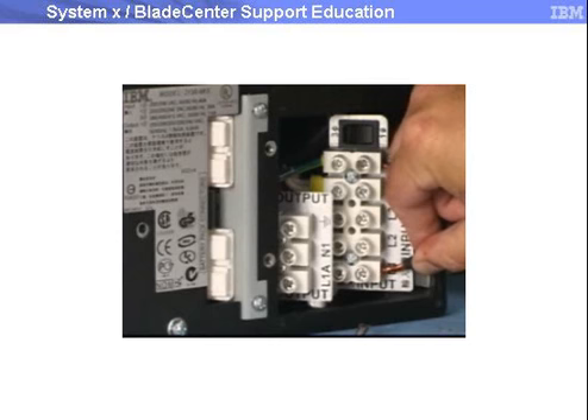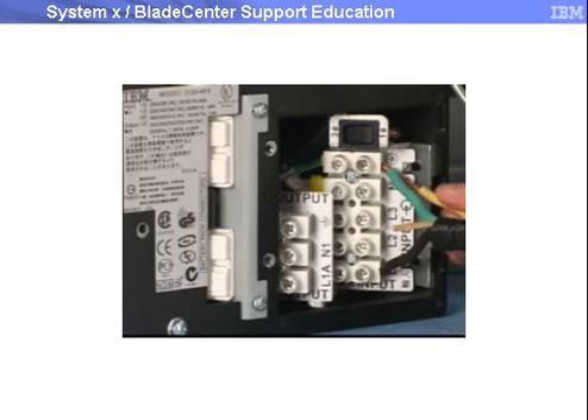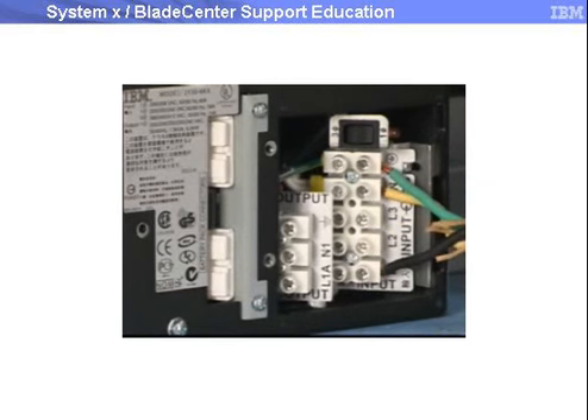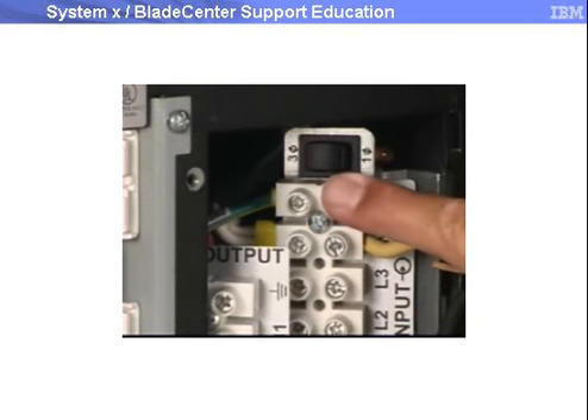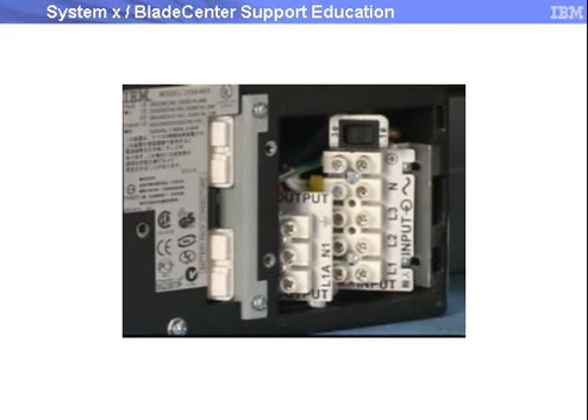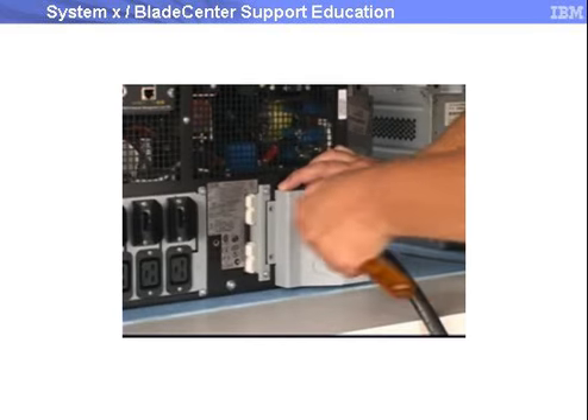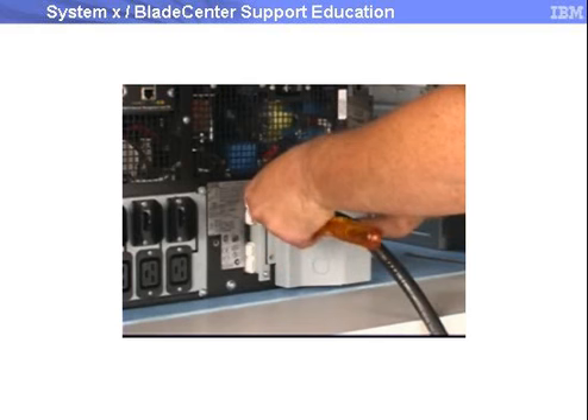If wiring to a single-phase supply, connect one supply wire to the L1 terminal block and the other supply wire to the N or neutral terminal block. Set the phase selector switch next to the terminal block to 1. Do not connect any AC input wires to the output terminal block, as this will damage the UPS. The output terminal block has labels L1A, N1, and ground. Replace the access panel.